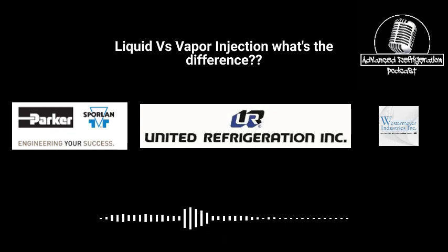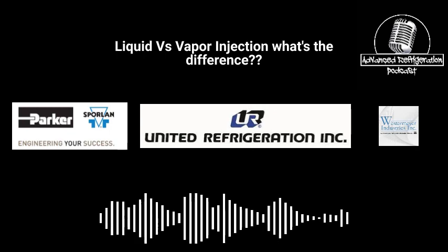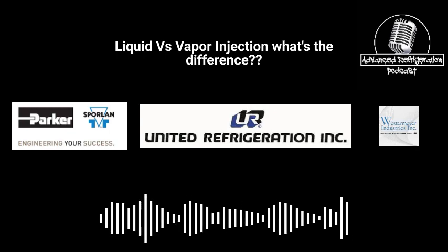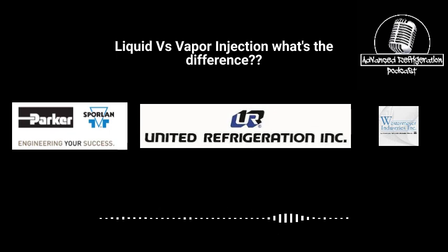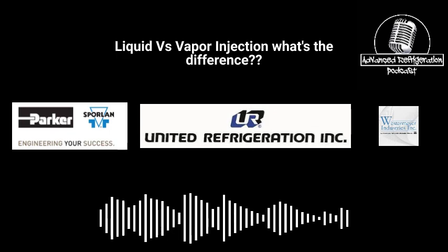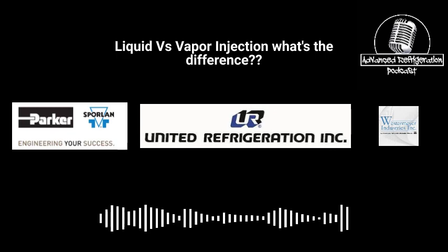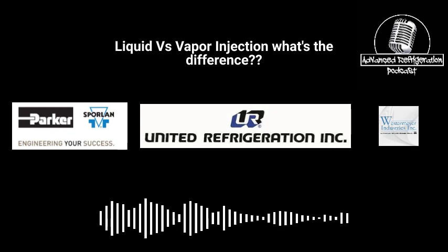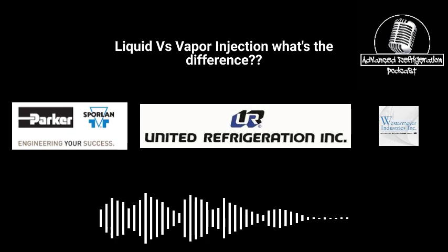Whatever, yeah, what is it? There's a whole math problem to figure out what it is. I don't know off the top of my head. I always have to look in the Carlisle book. You're talking about figuring out your interstage pressure? Absolute discharge pressure times absolute suction pressure, and then you take the square root, yeah, and that gives you your interstage pressure.